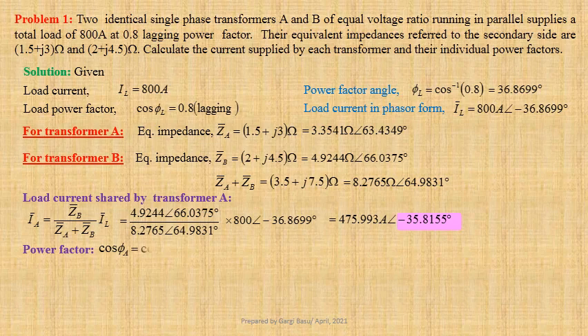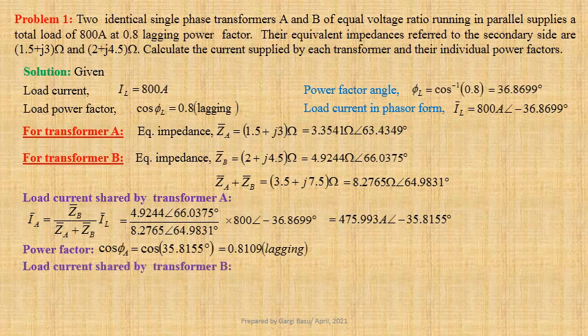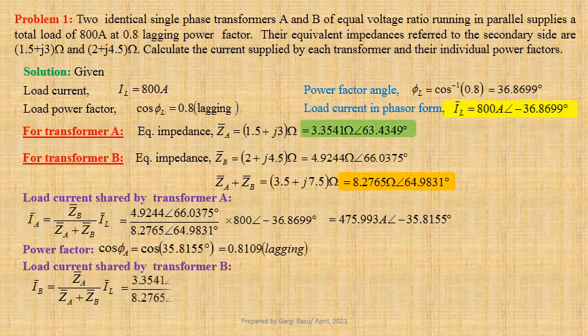Operating power factor of transformer A, cos phi A, equals cos of 35.8155 degree, that is equal to 0.8109 lagging. Load current shared by transformer B: IB equals ZA divided by ZA plus ZB, into IL. Using values we get 3.3541 at an angle 63.4349 degree, divided by 8.2765 at an angle 64.9831 degree, into 800 at an angle minus 36.8699 degree.